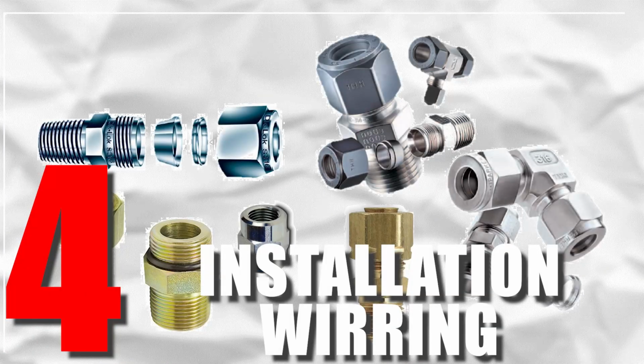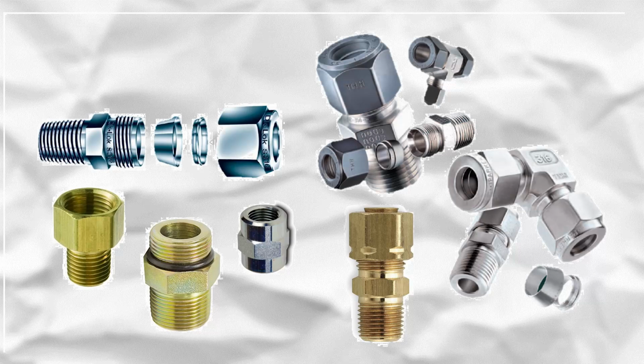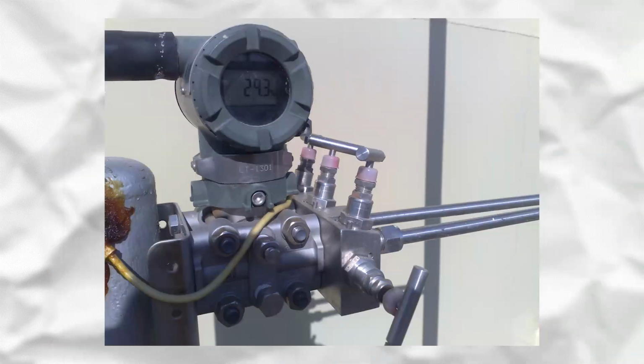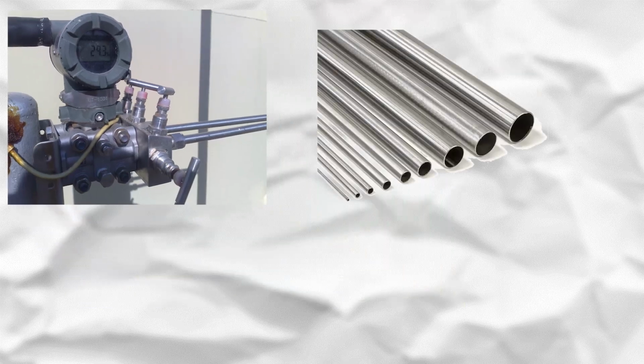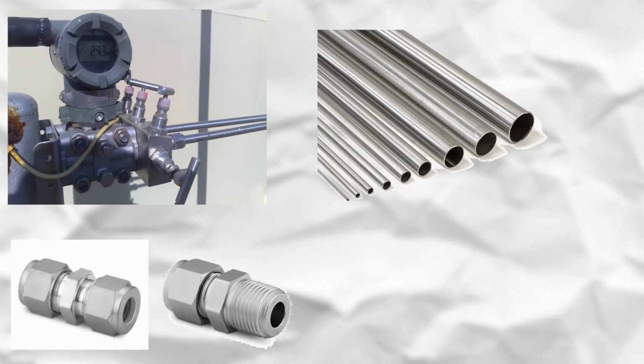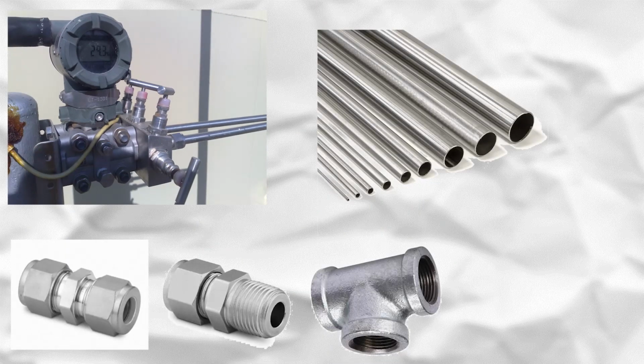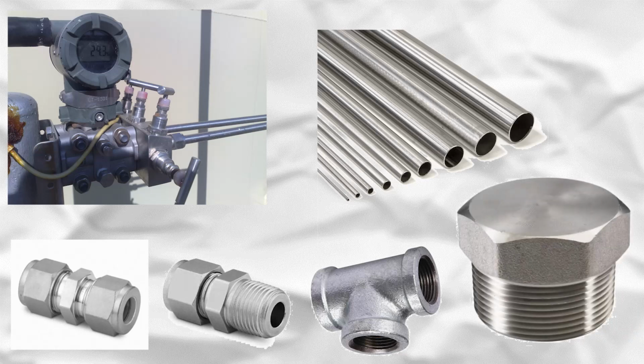In the fourth step, you get familiar with installation fittings and wiring equipment. Let's begin with hookup fittings. There are several types of fitting applied to install a measuring instrument on a pipe or a vessel. For example, for mounting a DP-type flow meter, we need tubes, union, male connectors, T-connectors, and plugs. In the designing stage, it is an instrument engineer's responsibility to draw a precise hookup drawing and then count the material takeoff or bill of material for all fittings.